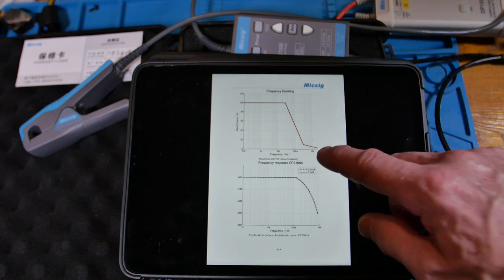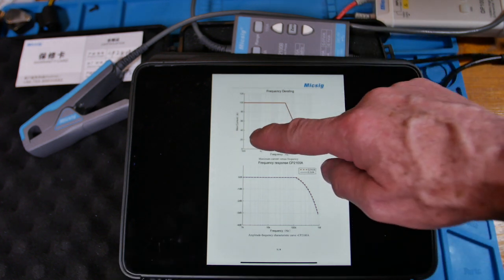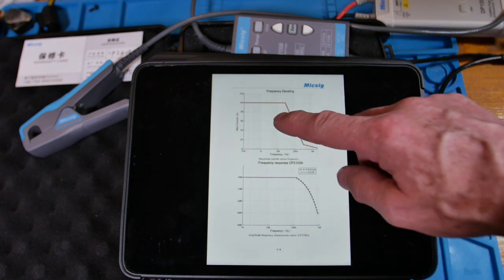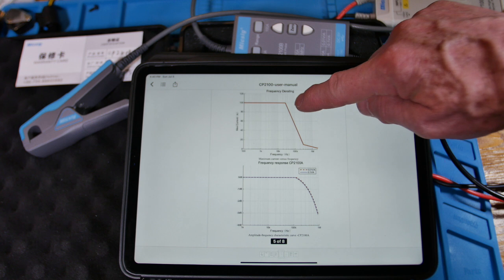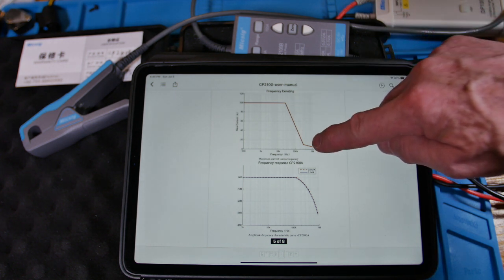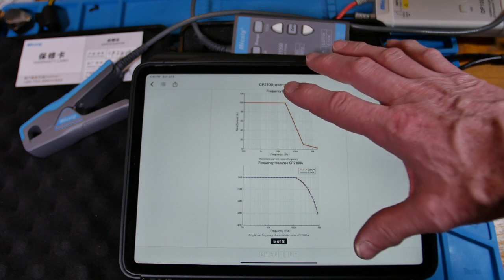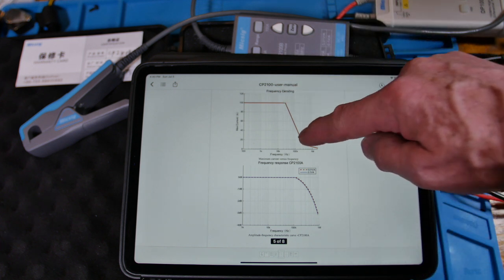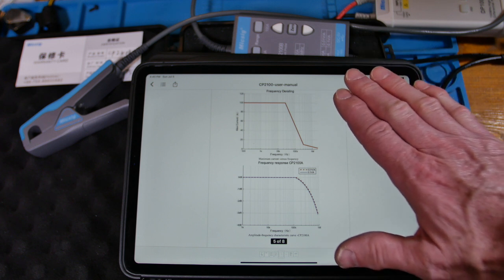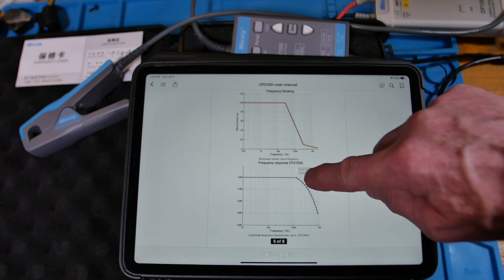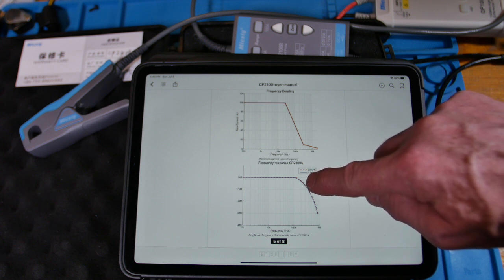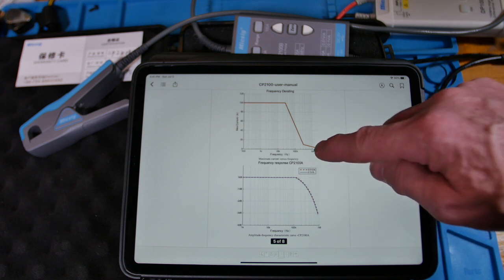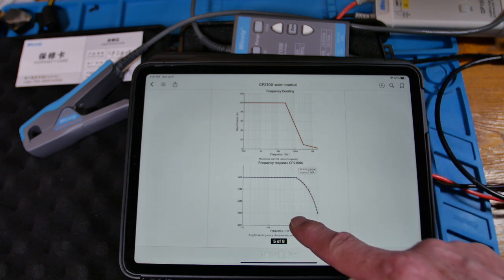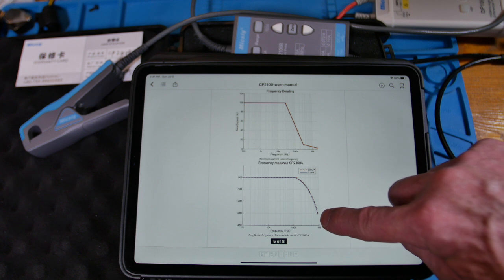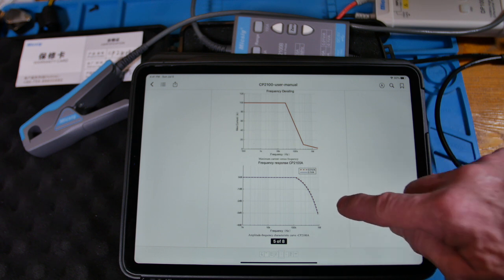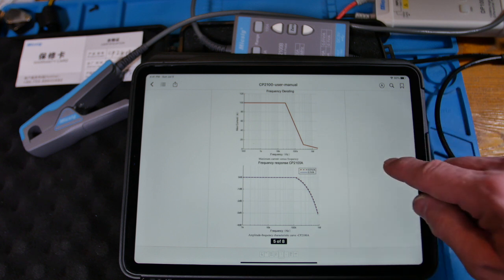Okay, so for the Micsig, this is the A version. This is current rating versus frequency. So 100 amps out to about 30 kilohertz, and then you derate down to this thing. So that's kind of like what Fluke was spelling out on that table. But if you compare this, even the 800 kilohertz version is better. And here's the roll-off. So they're showing at just over 100 kilohertz, 150 kilohertz starts to roll off. The minus 3 dB point is out here, and it shows about 800 kilohertz right there. So they really zoomed in on the roll-off portion.